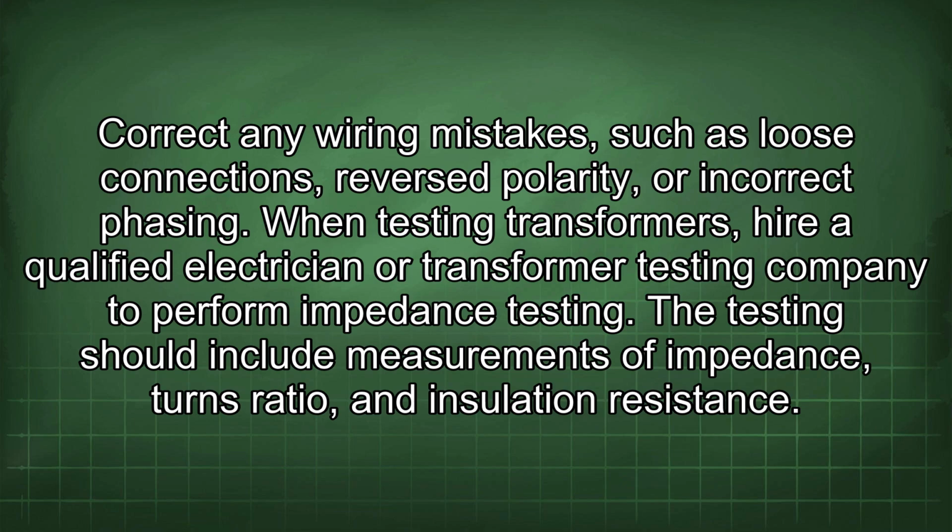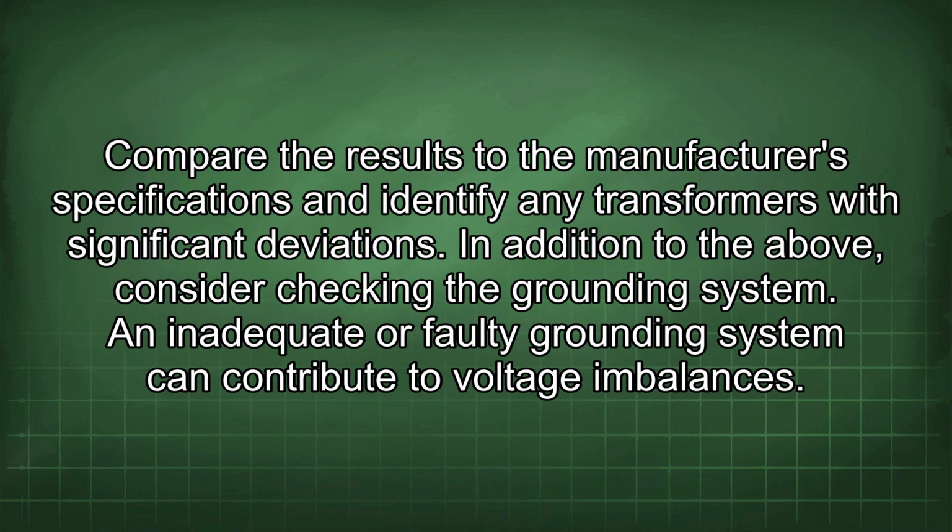When testing transformers, hire a qualified electrician or transformer testing company to perform impedance testing. The testing should include measurements of impedance, turns ratio, and insulation resistance. Compare the results to the manufacturer's specifications and identify any transformers with significant deviations.